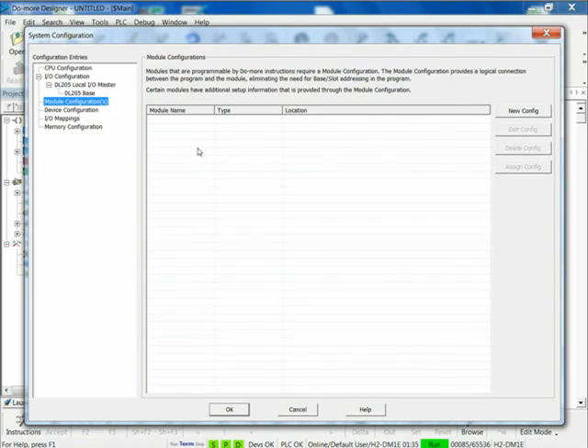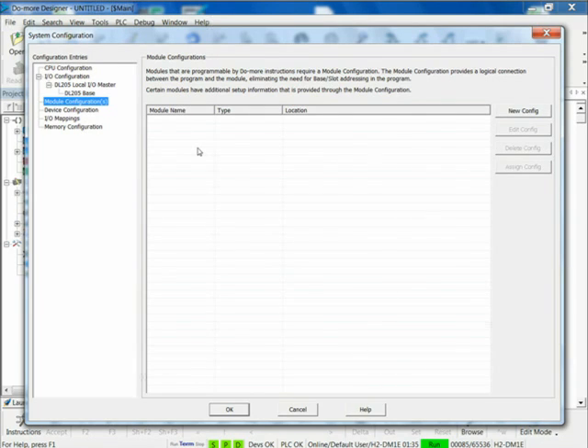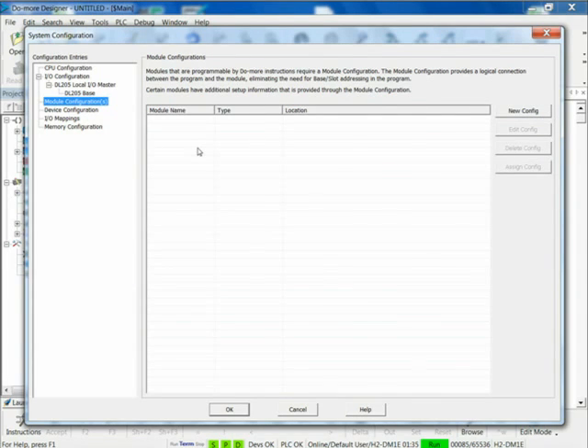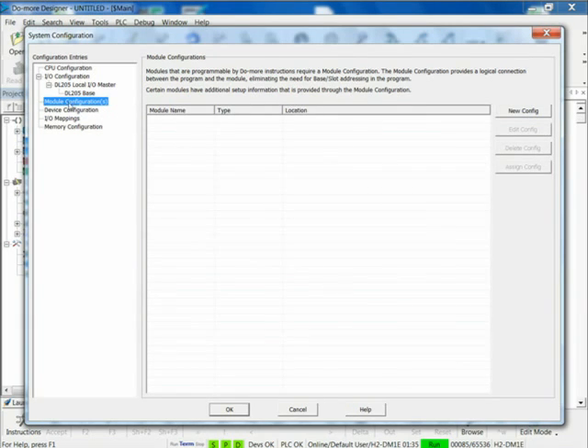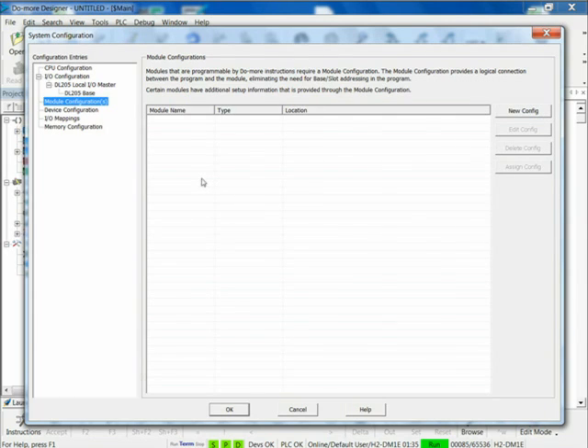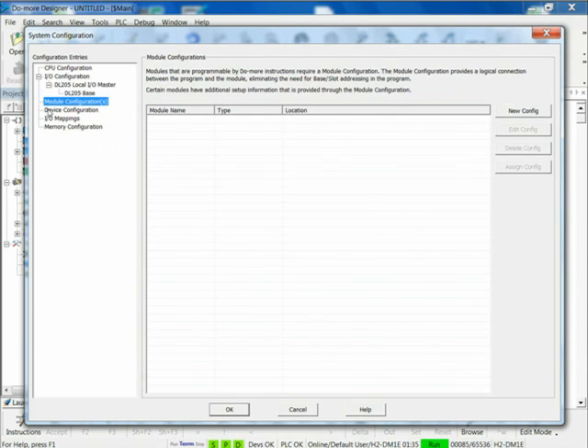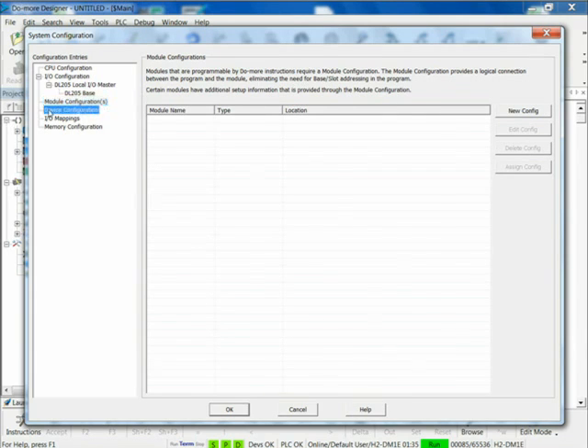If I were to stop right now and I plug a high-speed counter in here, then I take it Do-More will automatically load the device driver, or Designer will load it into the Do-More PLC, so that just works. And I can come in here and configure it if I want to. For a module like counter I/O, that's what this Device Module Configuration is for. You have to first configure the module to tell the module what it does. Then depending upon how you set up that module, you get different devices.